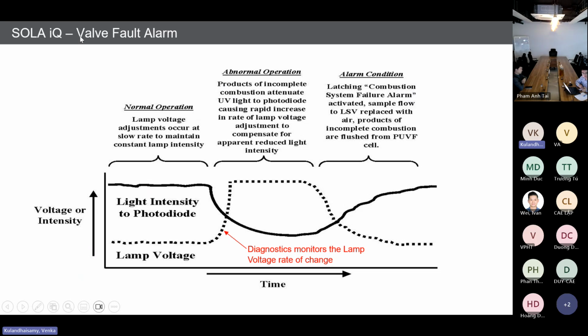That contamination can be eliminated by this operation. That's why we have a valve fault alarm. Our UV light emits a constant wavelength of light, and you can see the light intensity from the voltage versus time chart. The voltage or intensity of the UV light is very stable. In normal operation, lamp voltage adjustment occurs at a slow rate to maintain constant lamp intensity, the black dark line. Whenever there is abnormal operation, meaning your injection valve is leaking or the customer process has an excess amount of sulfur, probably the analyzer range is 0 to 100, but due to some process offset the customer process ppm level goes to maybe sometimes several hundred ppm or sometimes 5000 ppm range.